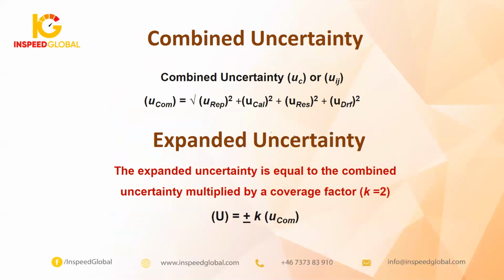Okay, how to get the combined uncertainty? Combined uncertainty is very easy to get. As you see, you get your repeatability, your calibration, your resolution, your drift from the previous table. You take the square of U repeatability plus the square of U calibration plus the square of resolution, and also for drift, and take the root of all this value. It is very simple to get the U combined, or combined uncertainty.